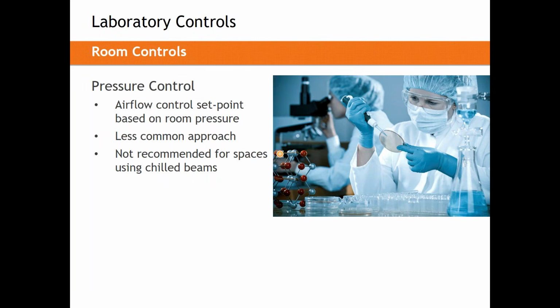It won't care what offset it uses. It will hit, let's say, minus 0.01 inches, but it doesn't care if it uses 1 CFM or 101 or 1,000. It will always tweak and tune those airflows to get you the right pressure. Now, the nice thing about this is it's closed loop and more accurate. It's really good in stable environments. So in an isolation room, this is a great control strategy because the doors are generally closed, traffic isn't very high in and out of these spaces, and it gets to do its job very, very often.